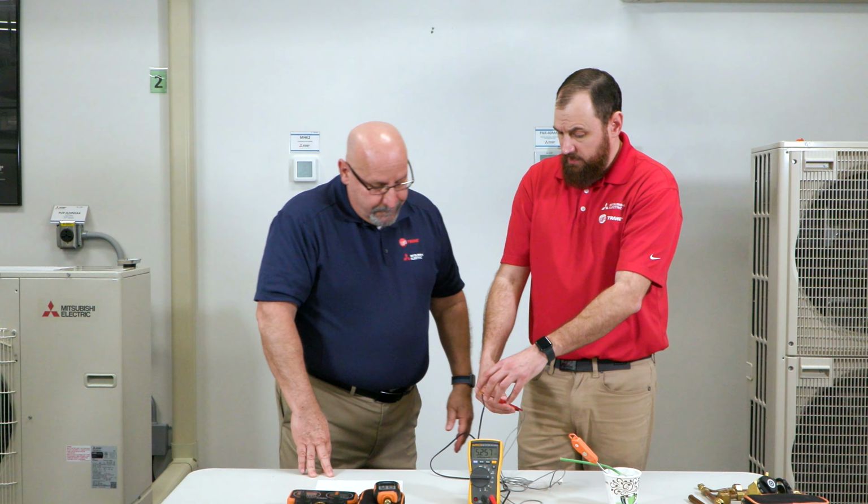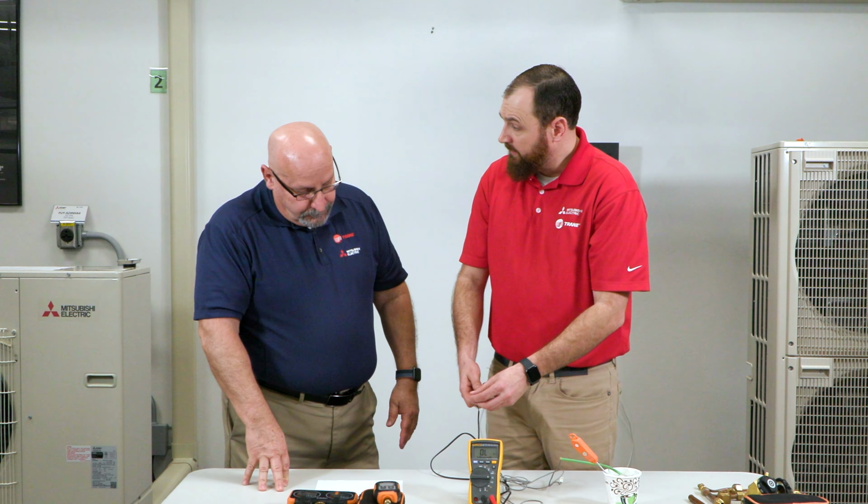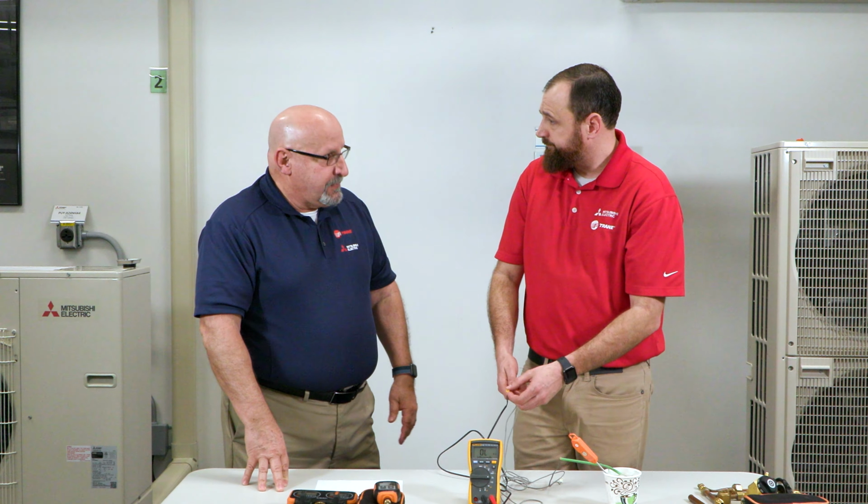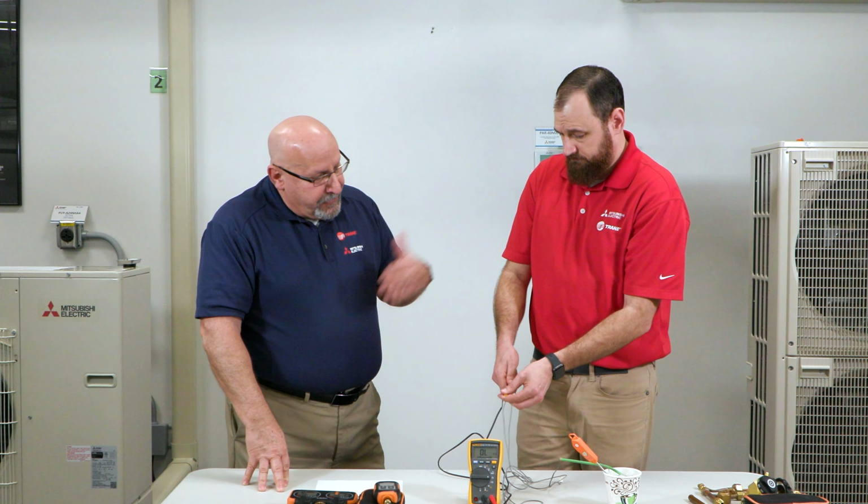Correct. And another good check if this thermistor is good or bad is if you're reading a 0 or an OL, then we've got a bad thermistor. Absolutely. And then again, a shorted thermistor will give you an out of range reading. Correct. For instance, our ambient temperature thermistor is measuring ambient temperature. So if the ambient temperature is 85 degrees, but with your resistance test, taking it to the chart, it tells you it's minus 10, we know we've got a problem. Exactly, you've got a bad thermistor.